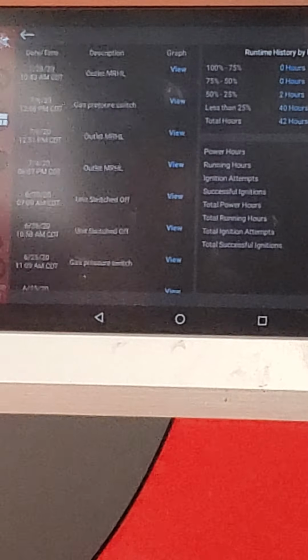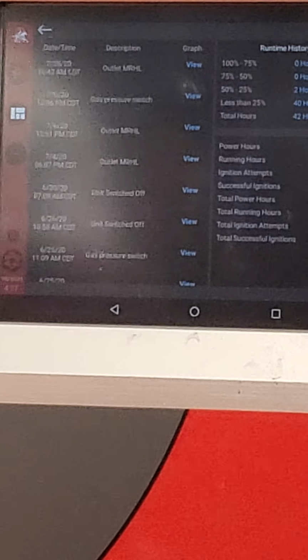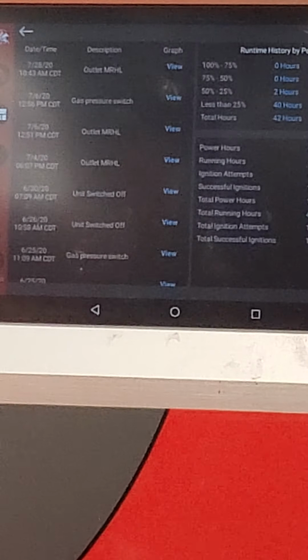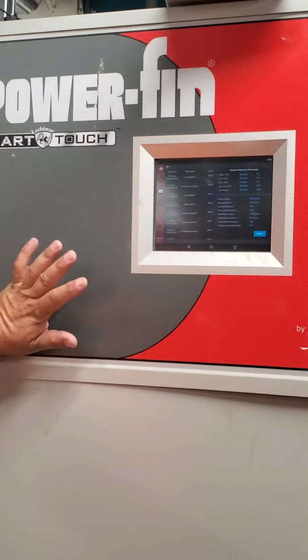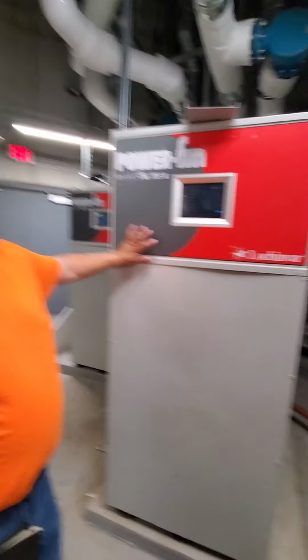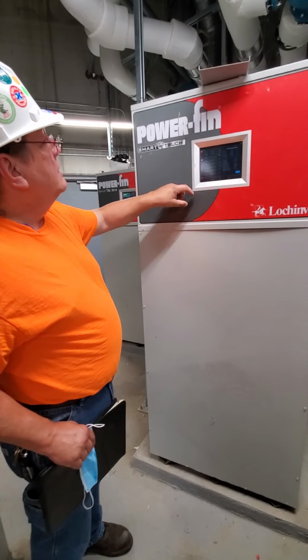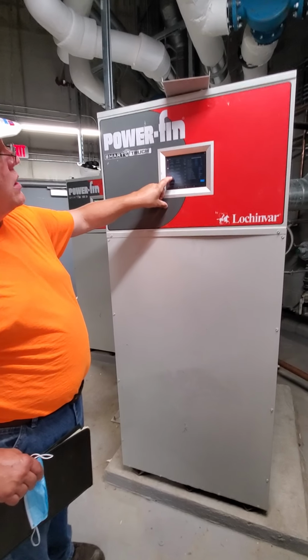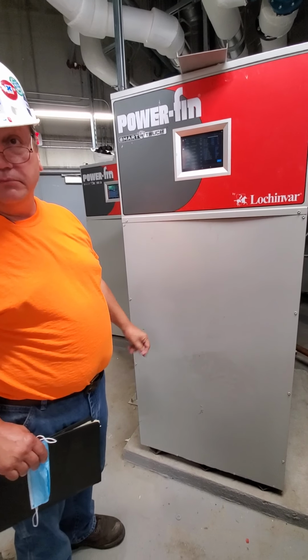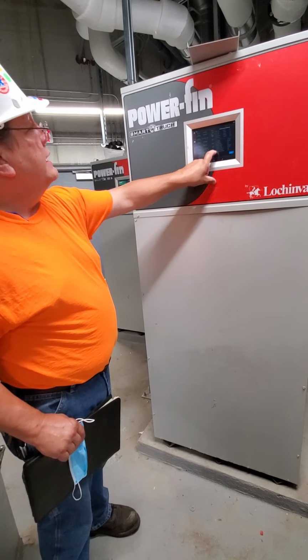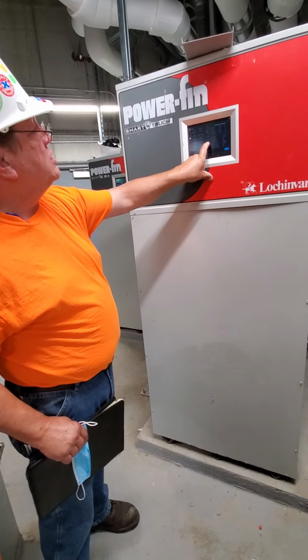You see one that says sensor. There are two high limits on this. There's one that has a temperature sensor on the water outlet. Then there's a mechanical high limit, which also measures on the water outlet. By code, this particular boiler has to have both sensors. And it'll tell you when it failed, what day it failed, what time of day. Morning, night. And if you want to look at more detail, you can press the view button.